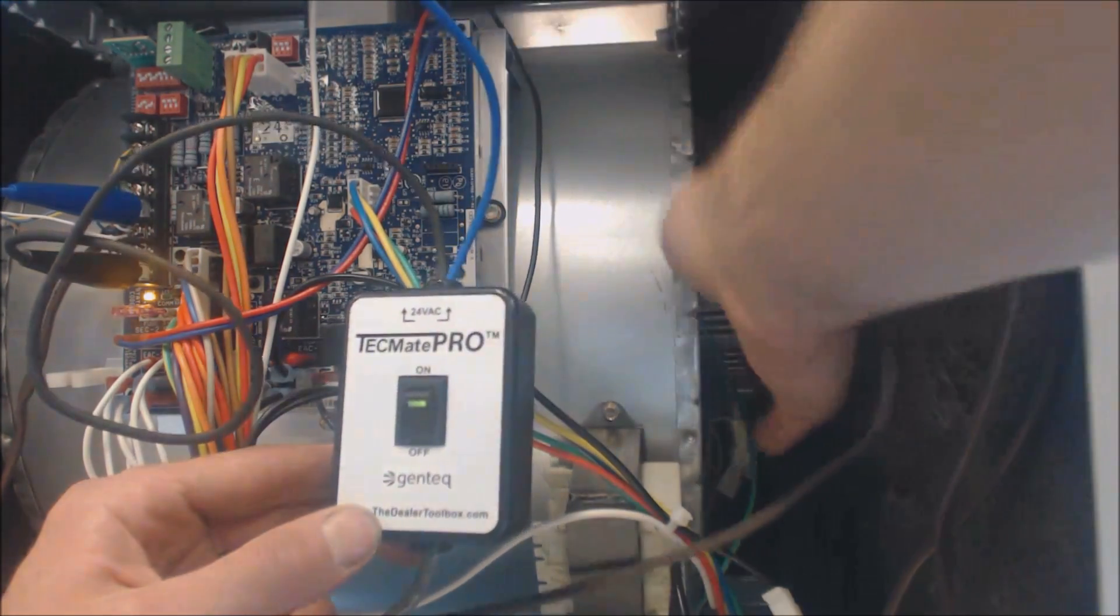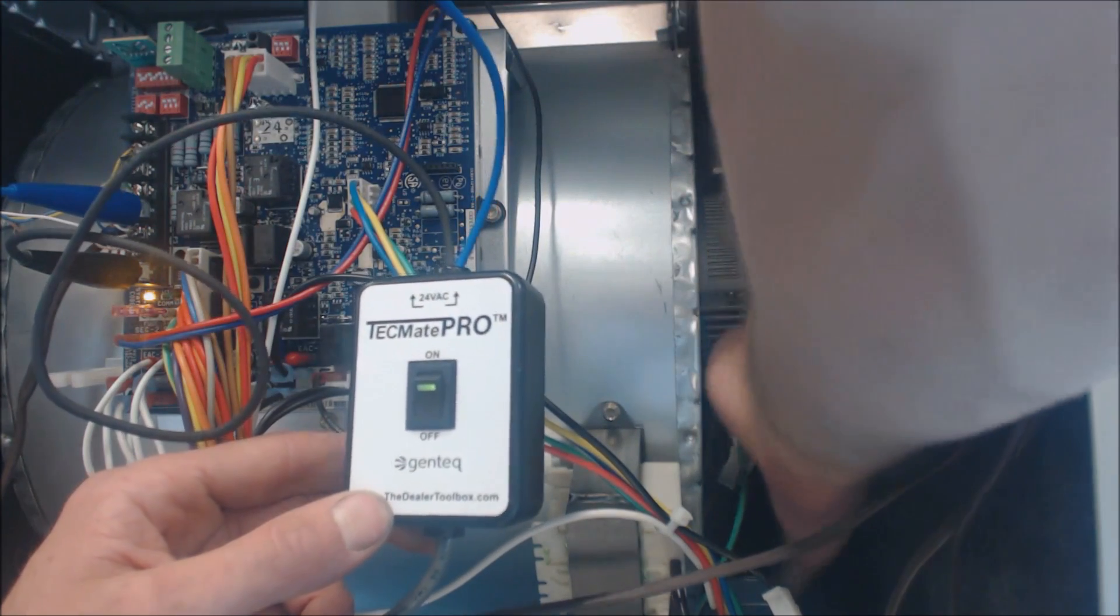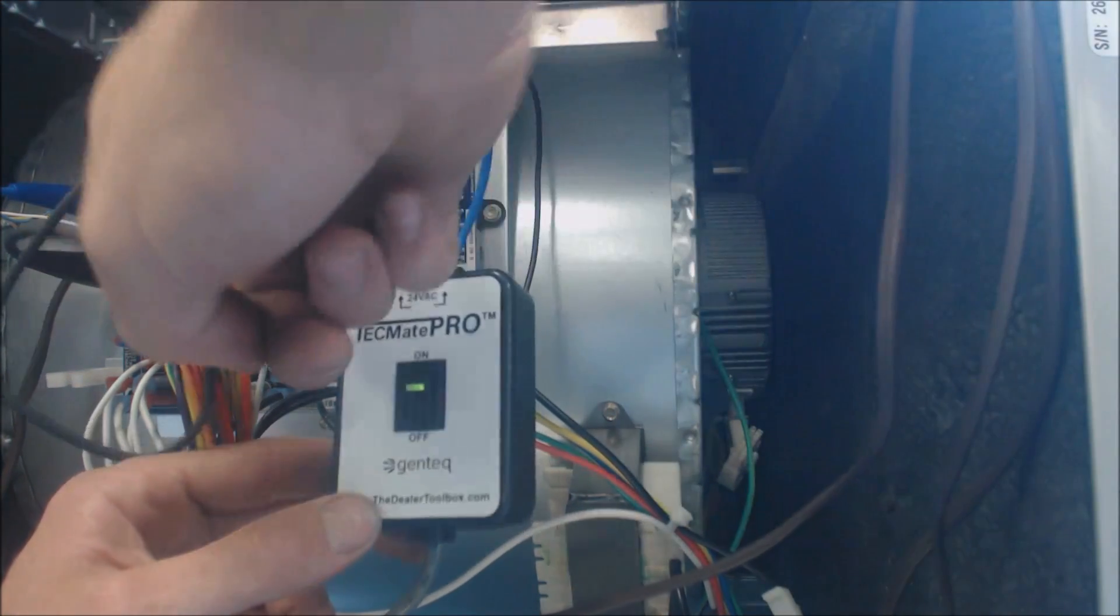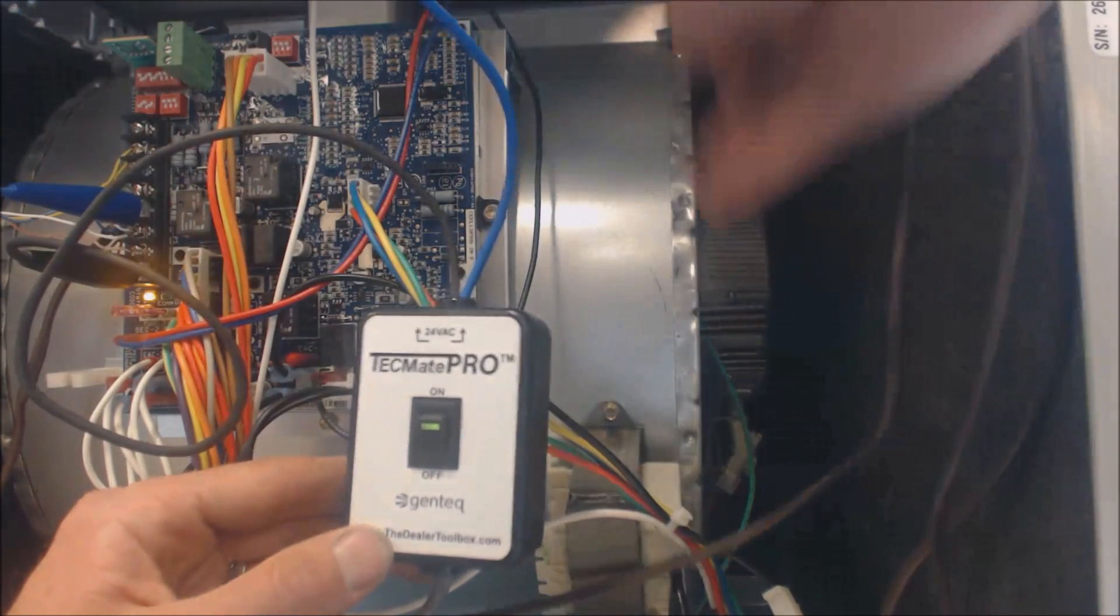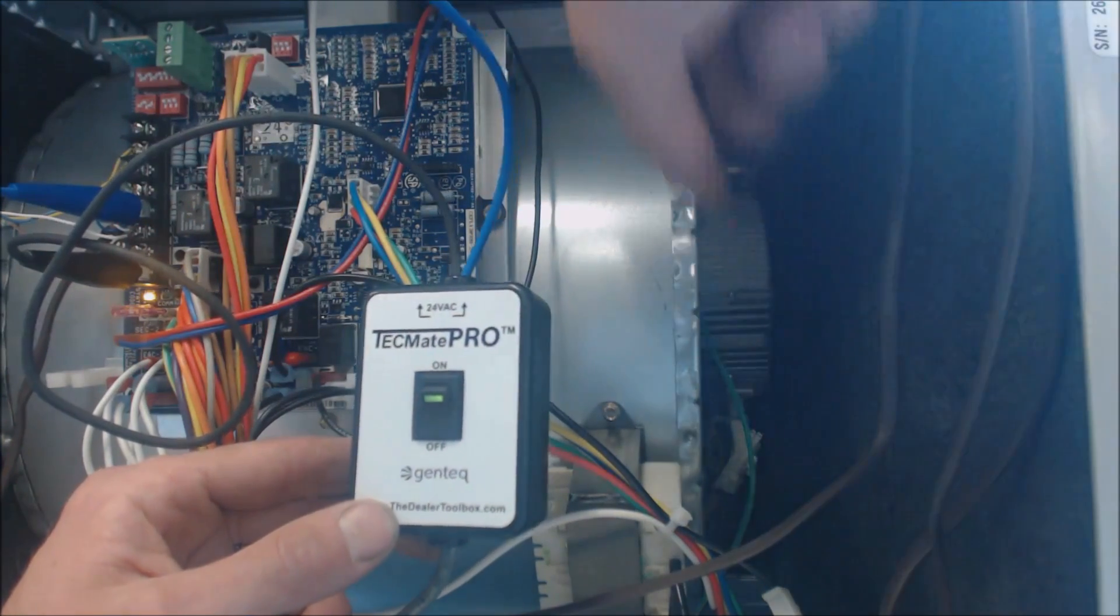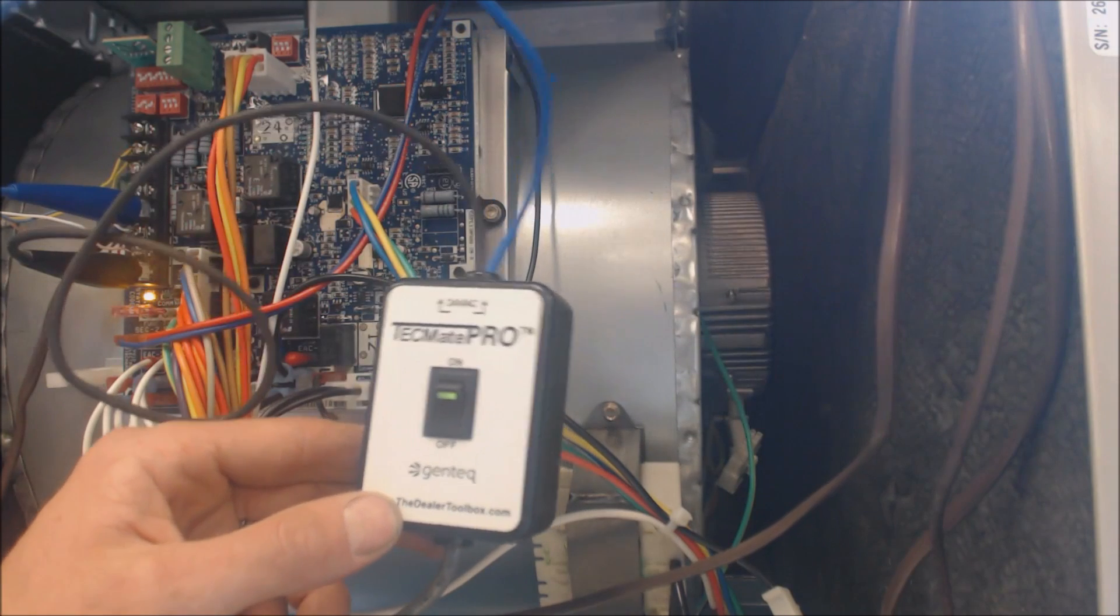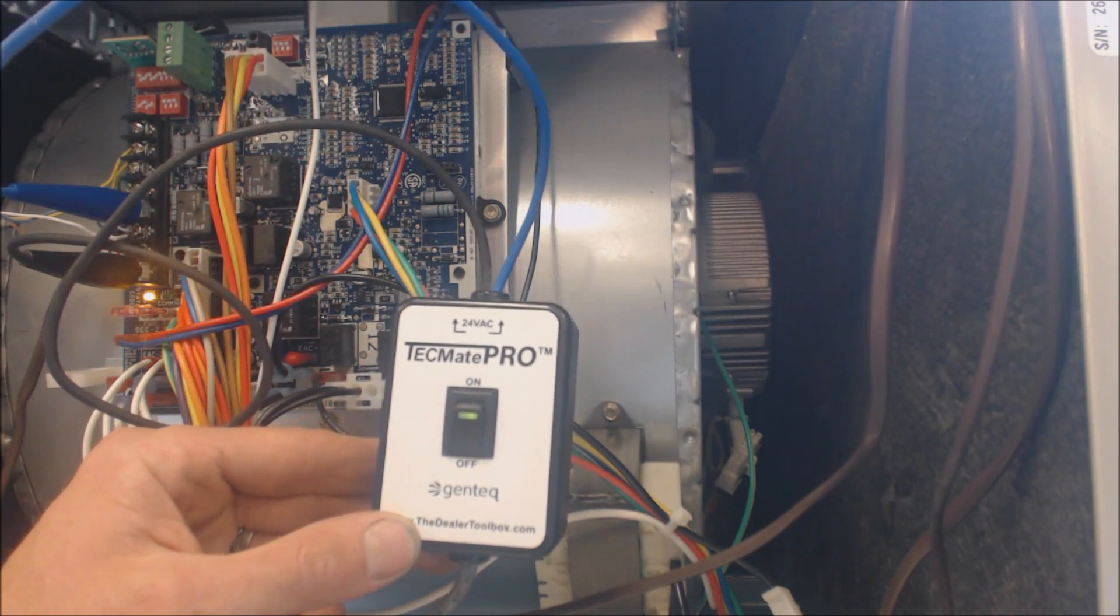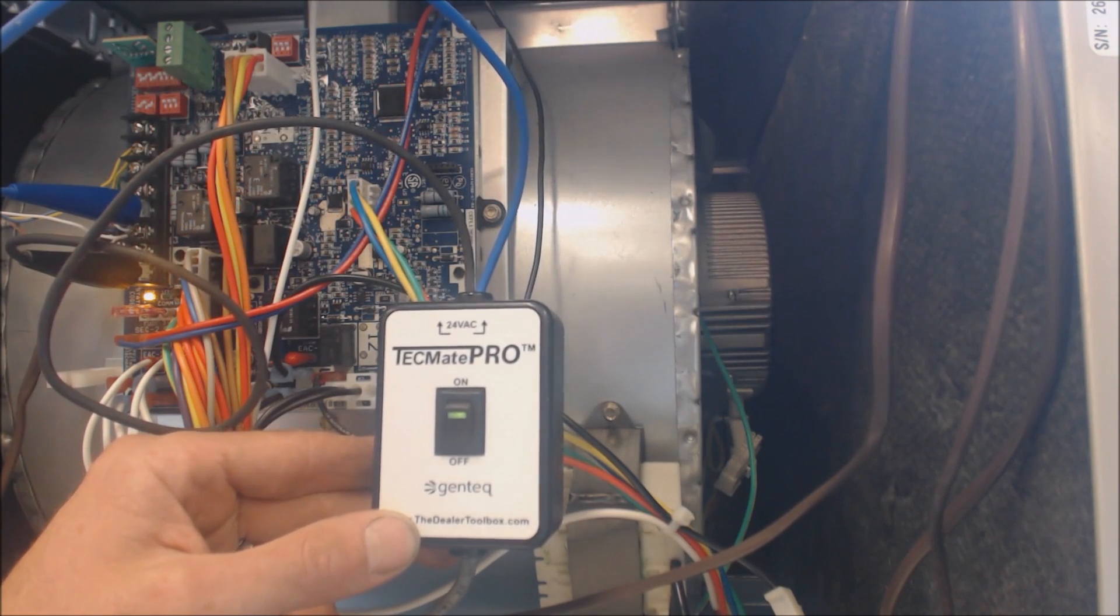The Genteq or the manufacturer actually recommends that you have a little wiring loop coming off of the connections - it comes down and then comes back up and then comes over to the control board. This way if you do have a drip come down the housing, it'll drip down and not go into the electrical part of the variable speed blower motor.